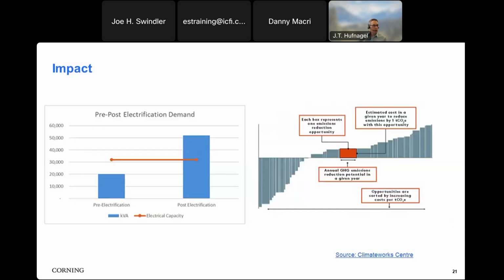And then, with electrification come potential constraints on the plant's electrical capacity. So understanding where that capacity is, the current state, and then if we were to electrify, would it push you up against your capacity? And this scenario would say, yes, if we electrified, we'd be well above our electrical capacity at this location and would need additional investment in upgrading that system as well.